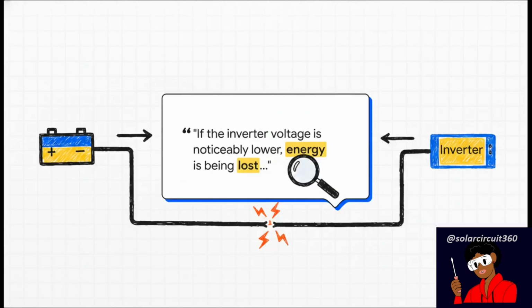This right here brings us to the golden rule of field troubleshooting. If the inverter voltage is noticeably lower, energy is being lost between the battery and the inverter. Finding that missing voltage between point A and point B is, hands down, the single most important diagnostic test you can run in your entire system. It tells you exactly where the problem lives.